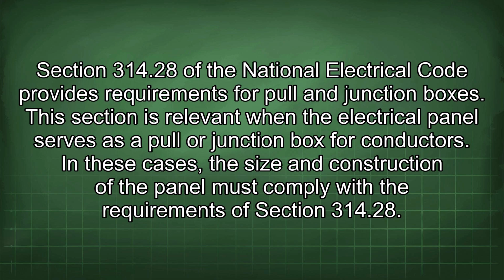Section 314.28 of the National Electrical Code provides requirements for pull and junction boxes. This section is relevant when the electrical panel serves as a pull or junction box for conductors. In these cases, the size and construction of the panel must comply with the requirements of Section 314.28.